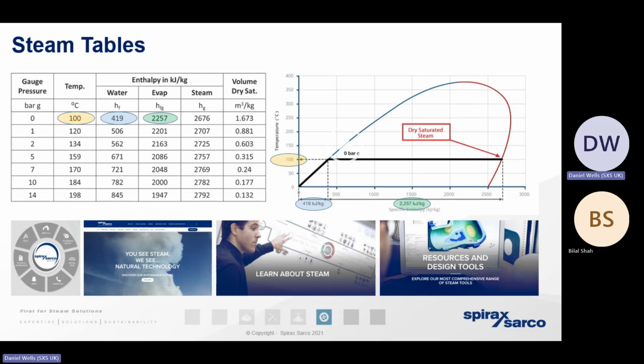The first 2 columns that you can see here bring together that pressure-temperature relationship that we spoke about. So I want you to think about generating steam in a kettle in your kitchen. We take 1 kilogram of water, 1 litre of water, that's got a volume of 0.001 cubic meters. We put that water into our kettle and bring it up to the boil. And we know from basic maths and physics that at atmospheric pressure, 0 bar gauge, water boils at 100 degrees, and therefore the temperature of the steam that's produced is also 100 degrees.